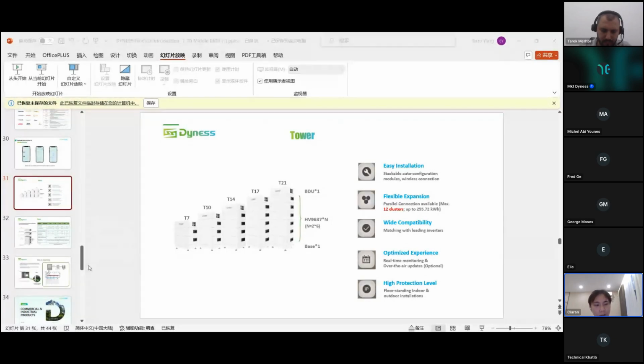Every single module is 41 kilogram. It's lighter than most batteries of the same size in the market of Lebanon. So this one has IP54, as I mentioned before, and also it has CAN, RS485 and RS232 communication, which allows it to communicate with the most mainstream brands of inverters in this market. So all of our batteries have a warranty of 10 years.